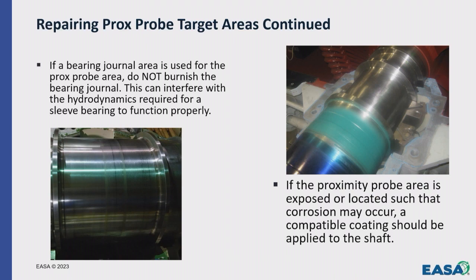Then also, if the proximity probe is exposed or located in an area that it sees a lot of air or moisture, like think about in a WP2, it's just inboard of the seals on the inside. That's a popular place for people to put it. There are coatings out there that are made specifically to work with proximity probes. You don't want to put just any enamel or epoxy on there. There are some that have some components that will affect your electrical runout also. So, you know, it is possible to coat, and I would recommend it if it's going to be outside of the sealed bearing containment. But be sure you're using something that doesn't impact the signal you hit.